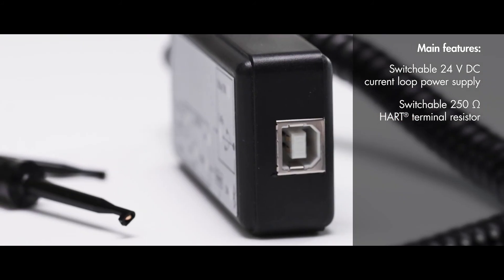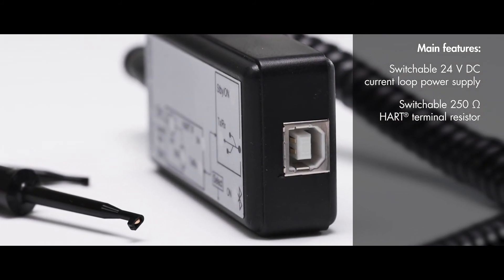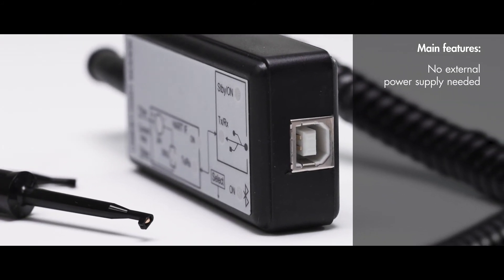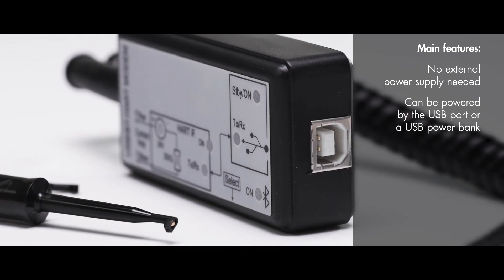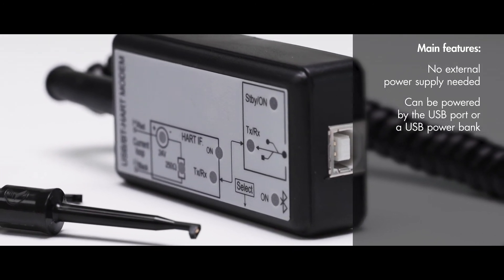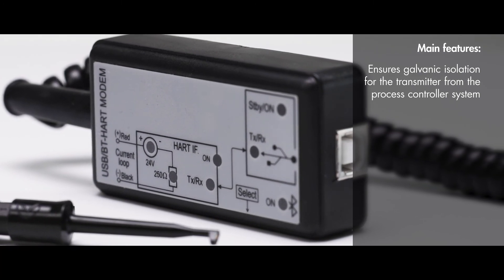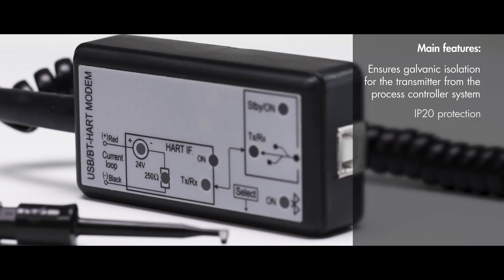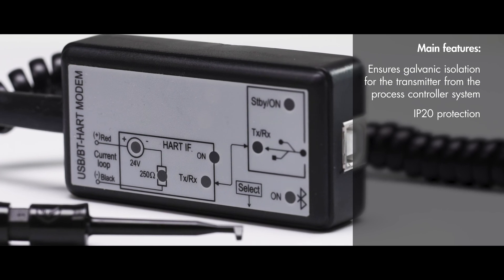Switchable 250-ohm HART terminal resistor. No external power supply needed. Can be powered by the USB port or a USB power bank. Ensures galvanic isolation for the transmitter from the process controller system. IP20 protection.